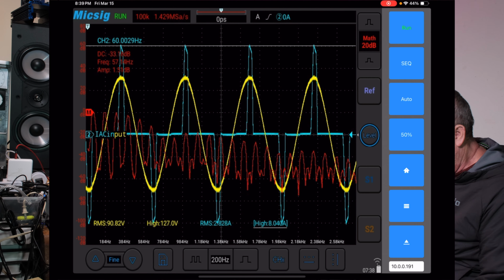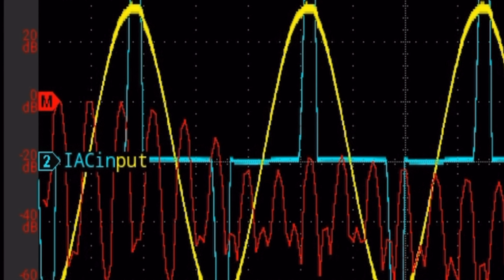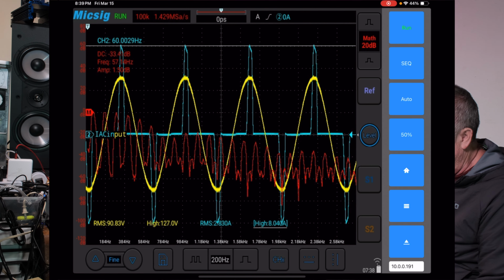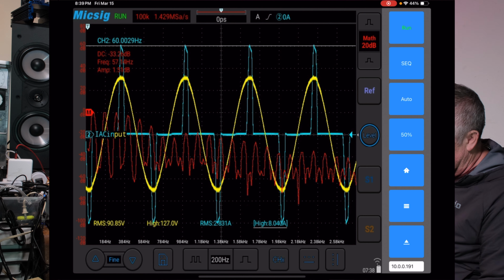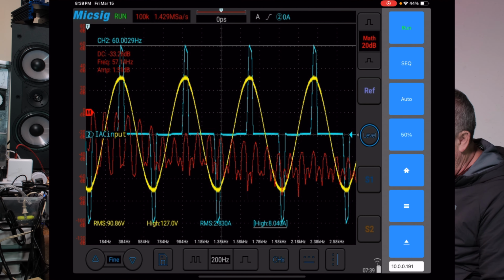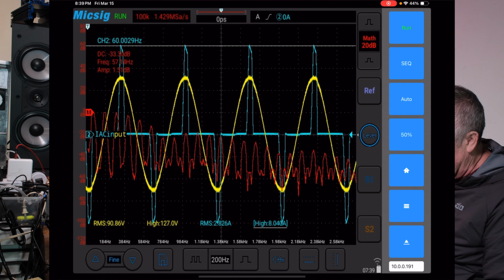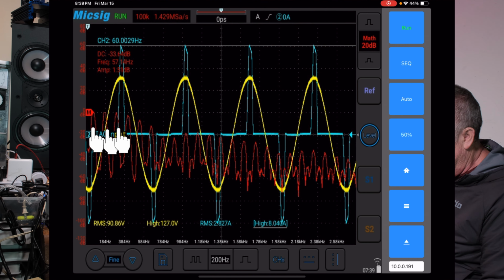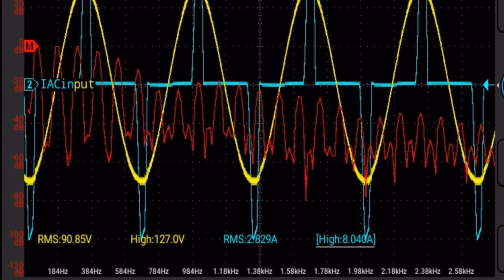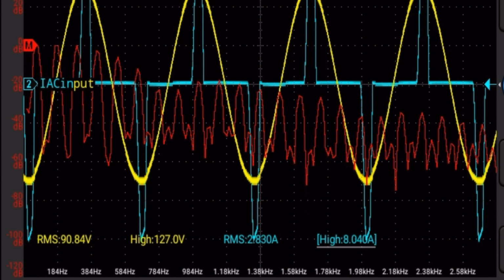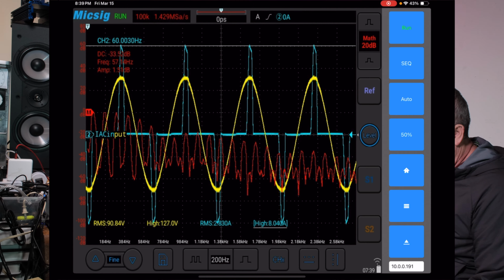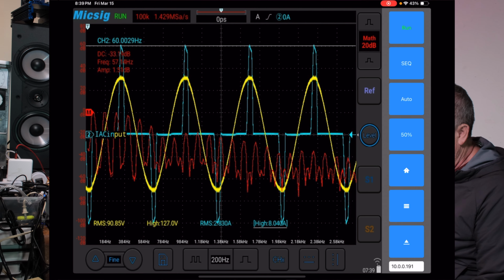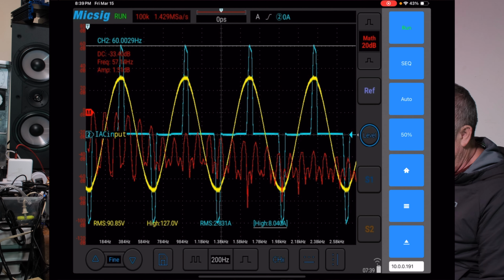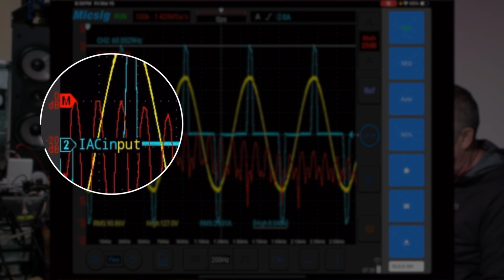Notice there is no large fundamental at 60 hertz. We'd like that, because we like our power transferring at 60 hertz, the line frequency, the sine wave of our voltages, but it's not. You can see it's down around 0, and the first 3 or 4 harmonics are pretty close to the same value. Then it rolls off about 20 dB for another 5 cycles, then drops off again a little bit. What that's showing us is the current is all noise, very noisy. That peak current pulse, the first 3 or 4 harmonics, maybe 5, are pretty much making up the content of that amplitude.